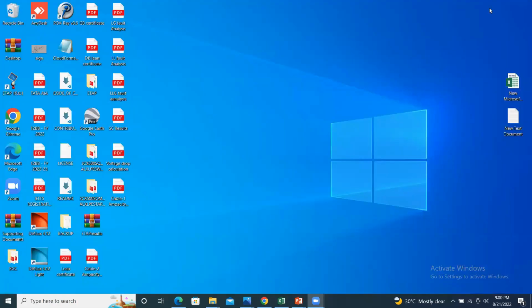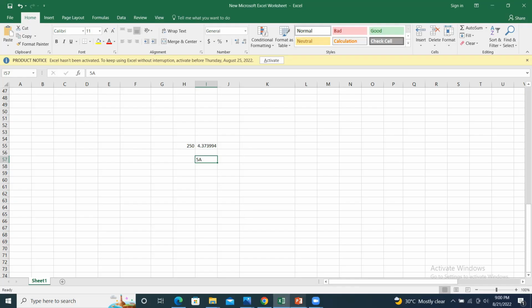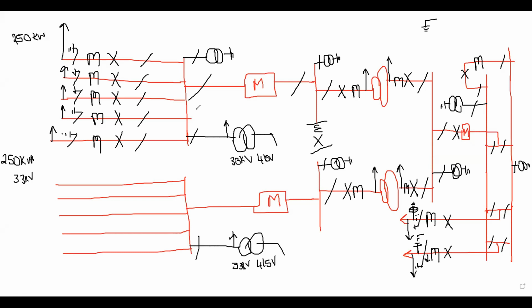So in this case, by checking that, and also other conditions like the market availability of the CT and the breaker for the auxiliary transformer, we will not have the CT. We are giving the protection through the HG fuse, horn gap fuse. We will select the HG fuse based on the rated current. So this fuse will melt and trip. So the protection for the auxiliary transformer is the 33 kV HG fuse.